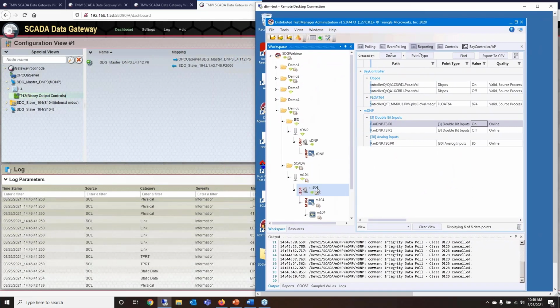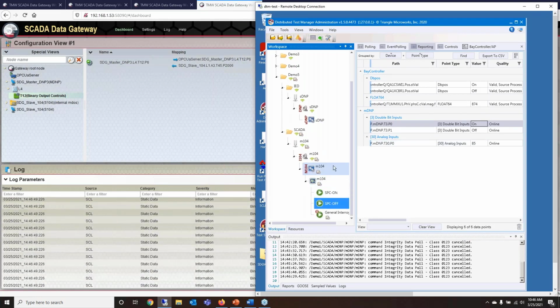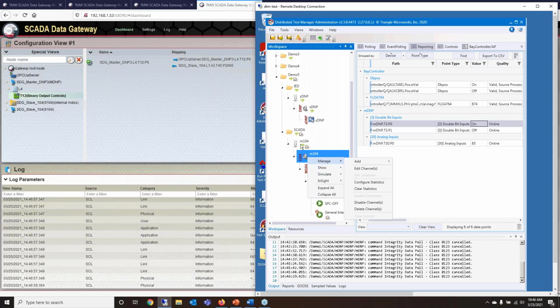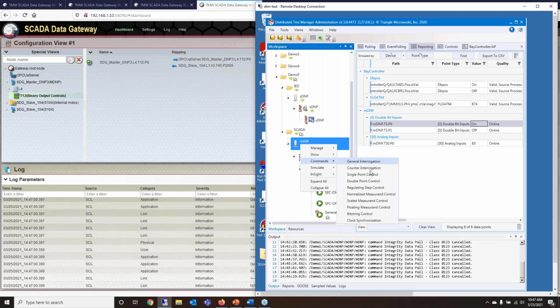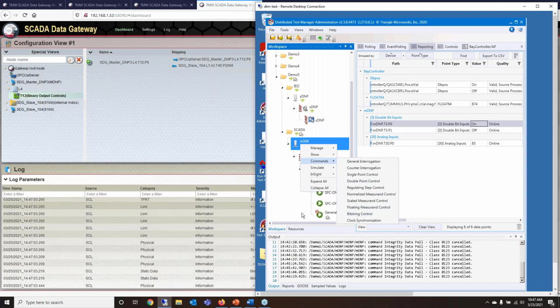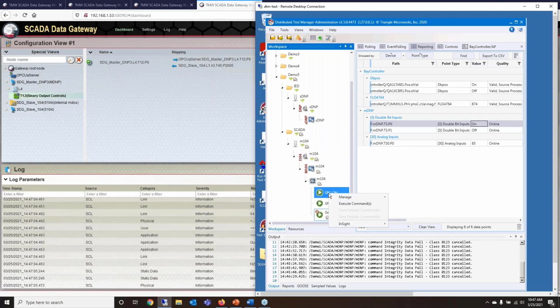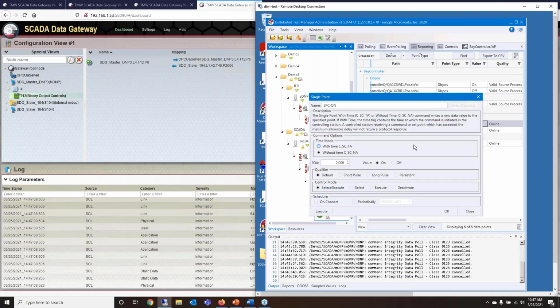This time I'm not going to be dealing with the IEDs or downstream devices and changing values inside their database to propagate the event. I'm actually going to issue a control from the controlling station. To do that, you right-click on the master you want, go to commands, and you can set up any commands you'd want to issue down. For this, we're doing an operation on a single point.